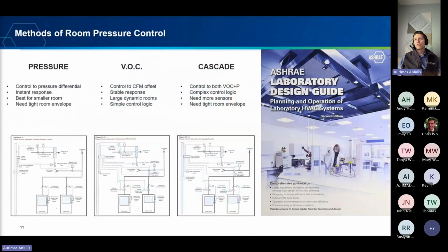When it comes to room pressure controls, there's 3 types of room pressure controls. First one is direct pressure control, where we're controlling to a pressure set point. The second one is volumetric offset, where we're just using the supply and exhaust differential into a space, and we're trusting that the valves are accurate and doing the thing. And the last one is what they call sometimes cascade or progressive or VOC with pressure override. And it's basically the combination of the two, which gives you the best of both worlds. Now, the only drawback to that is your control sequence of operations becomes really complex and requires a certain level of skill and ability to execute successfully out in the field.